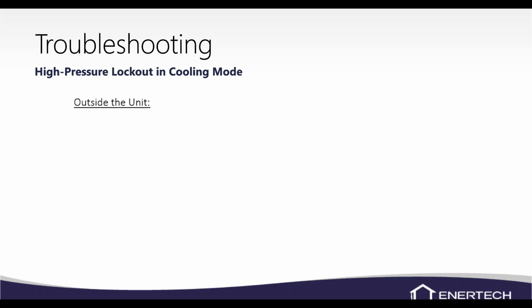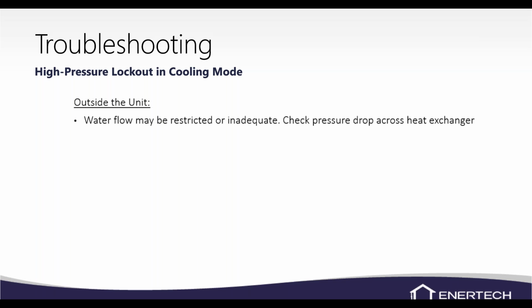So the loop field, or if you've got an open loop, the pump and dump, but we're going to be looking at the source side of things in cooling mode, high pressure lockout. So water flow. Again, make sure we're always installing pressure temperature ports so we can check pressure drop. Make sure we've got proper water flow. Feel your pumps, see if they're hot. Check your amp draw on your pumps, see what kind of amp draw they're moving.